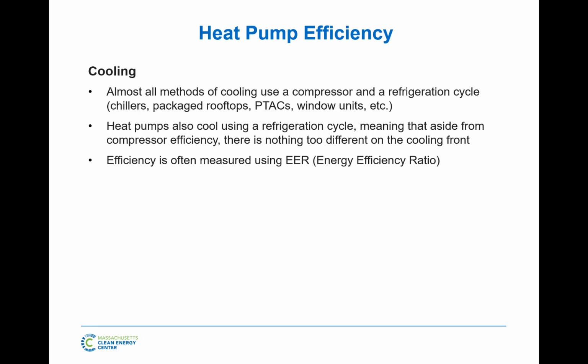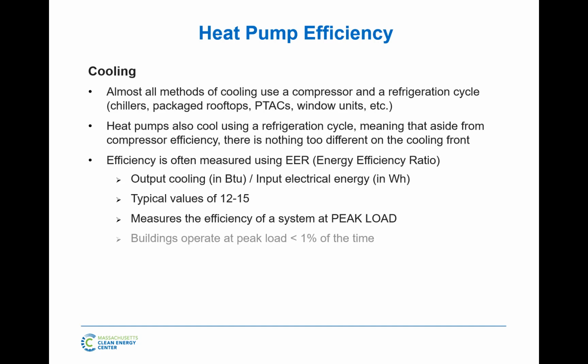So what that means is, excuse me, let me get through this. We talked a little bit about the EER. The EER is an efficiency measurement. So AHRI, which is the body that governs this, says, okay, manufacturer A, give me your unit. I'll run it at full load. There's certain standards, and I'll figure out how many kilowatts of electricity you need in to deliver a certain amount of cooling. That's what the EER is. Almost everything has an EER rating, whether it's a water source heat pump or VRF. Typical values for us is in the 12 to 15 range, us being the VRF folks.